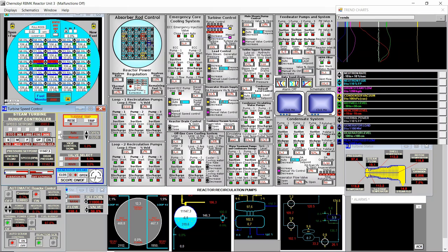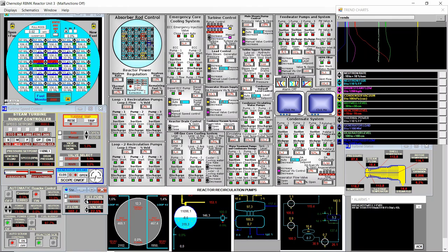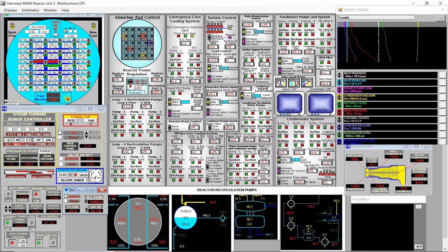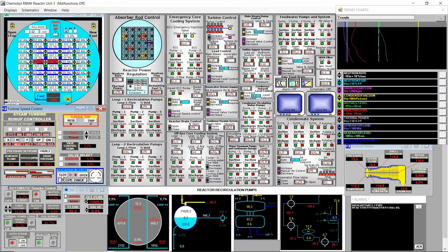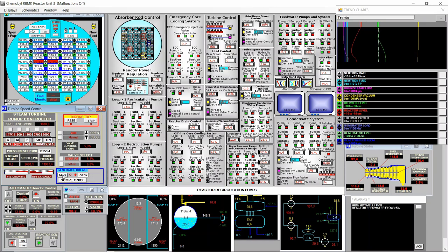When the velocity stabilizes in automatic control we connect the oscilloscope and synchronize. I cannot synchronize yet — the pressure on the drum needs to be high enough. I set the set point to 12,000. I switch on the oscilloscope and close the breaker just before the top dead center. The first attempt didn't close, so I try again. Now the breaker closes, it synchronized — we are generating one megawatt. I increase power to 15 percent in the reactor.